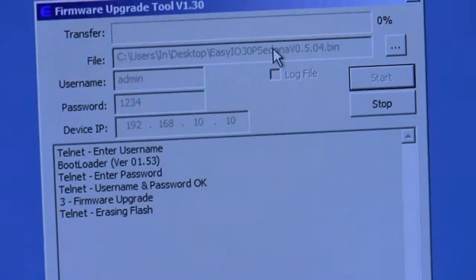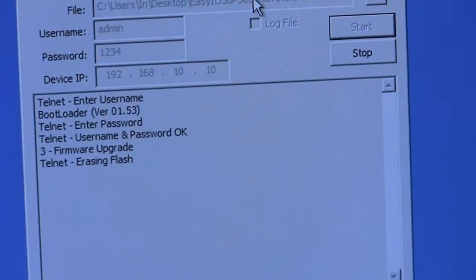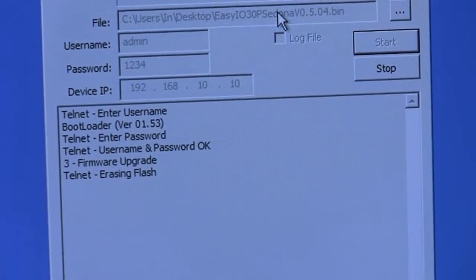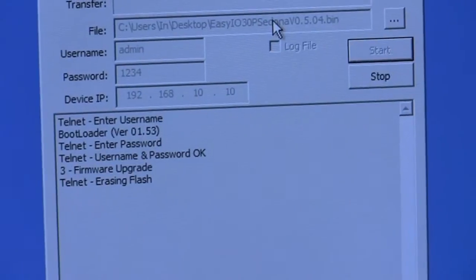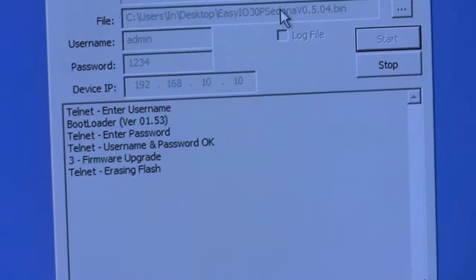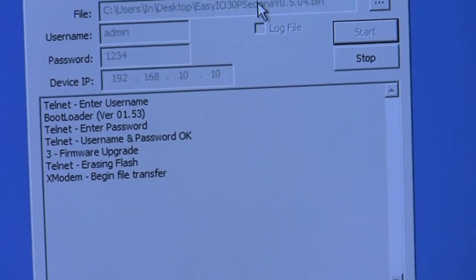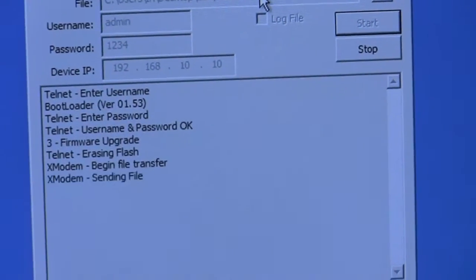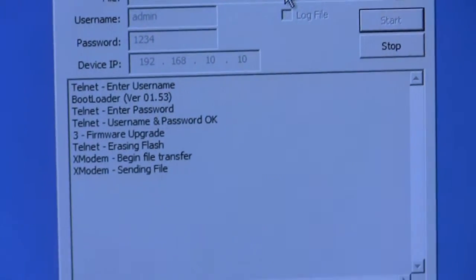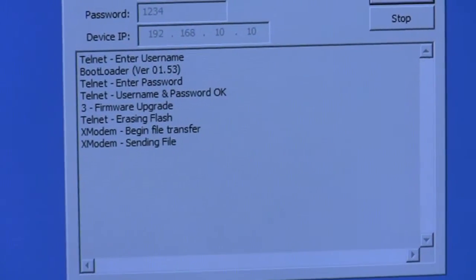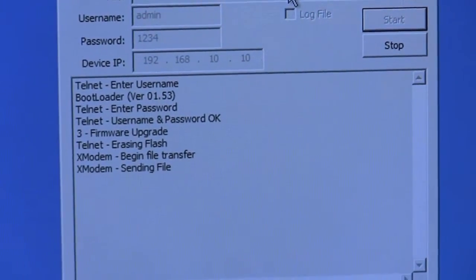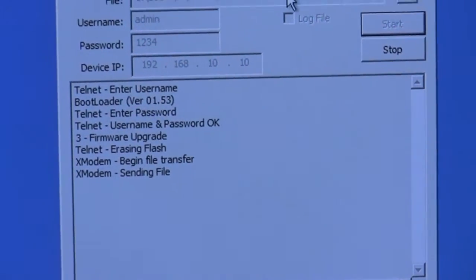And what it will do is just erase the flash again. And it will shortly just start to install a 1MB BIN file. In that file, there is a full BACnet stack. There is Modbus. There is Modbus Slave. There is Sedona. There is the Sedona engine. And all the kits. Everything is going in now. Which is pretty awesome when you think about it.